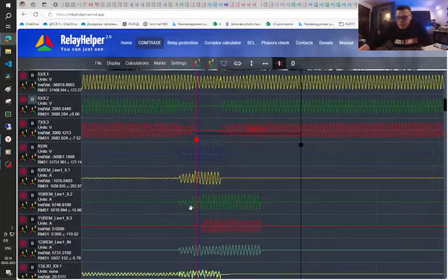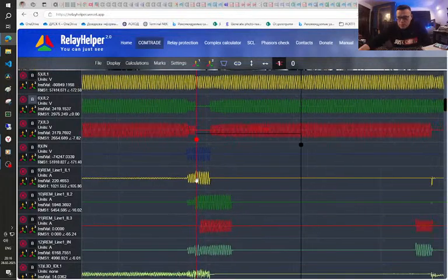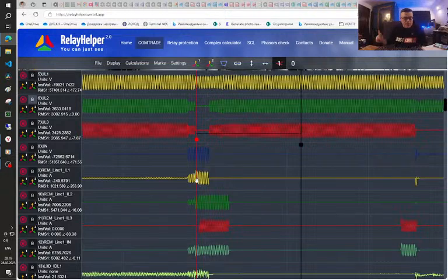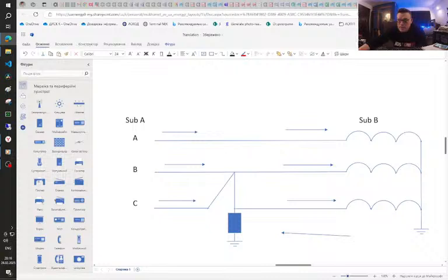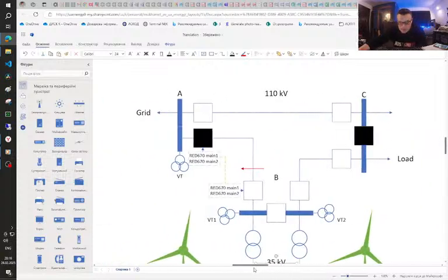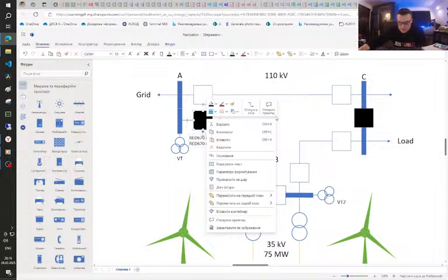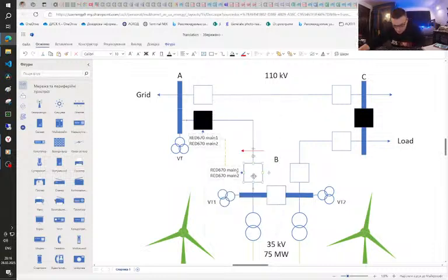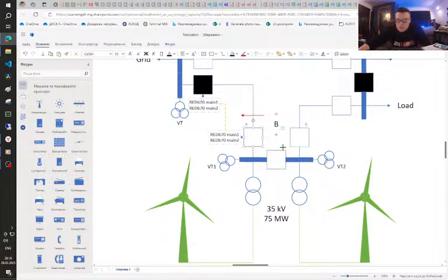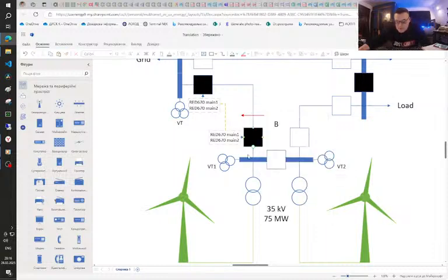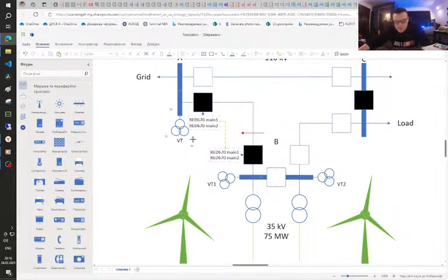So I believe I described all I want, and the final thing that I want to add is the things that I learned from this particular case. The first thing is nobody expected that a wind farm would produce electric power while disconnected from the grid.